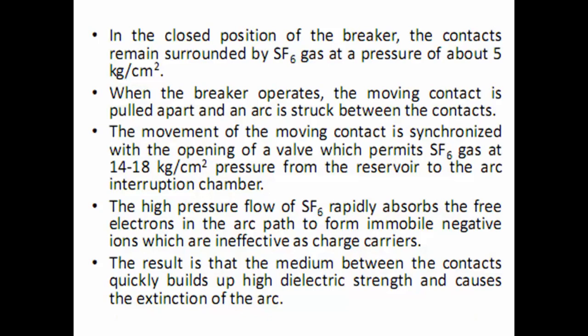Like in the closed chamber, the breaker contacts remain surrounded by SF6 at a pressure of about 5 kg per centimeter square. When the breaker operates, the moving contacts are pulled apart and an arc is struck between the contacts. The movement of the moving contact is synchronized with the opening of the valve, which permits SF6 gas at a pressure of 14 to 18 kg per centimeter square to flow from the reservoir to the arc interruption chamber.